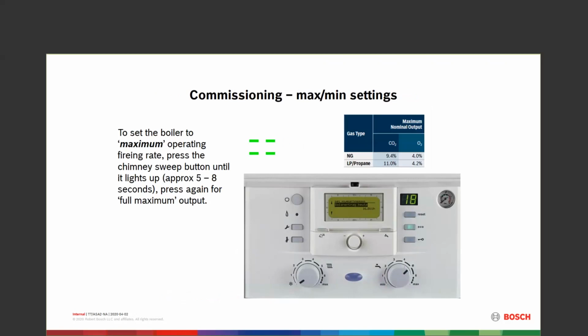The analyzer's already in, the boiler's already running. In high fire, you are looking for 9.4% CO2 on natural and 11% CO2 on LP. So as I stated earlier, we're going to take that same chimney sweep, the man with the ladder. You're going to push and hold it. It's going to light up.